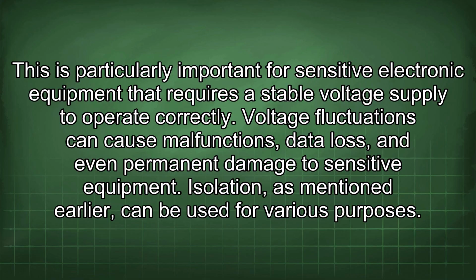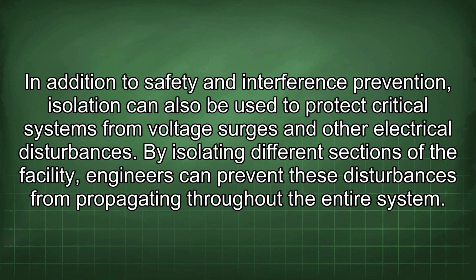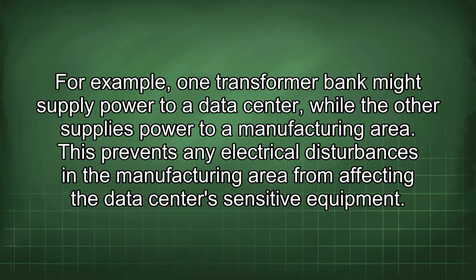Isolation, as mentioned earlier, can be used for various purposes. In addition to safety and interference prevention, isolation can also be used to protect critical systems from voltage surges and other electrical disturbances. By isolating different sections of the facility, engineers can prevent these disturbances from propagating throughout the entire system. For example, one transformer bank might supply power to a data center, while the other supplies power to a manufacturing area. This prevents any electrical disturbances in the manufacturing area from affecting the data center's sensitive equipment.